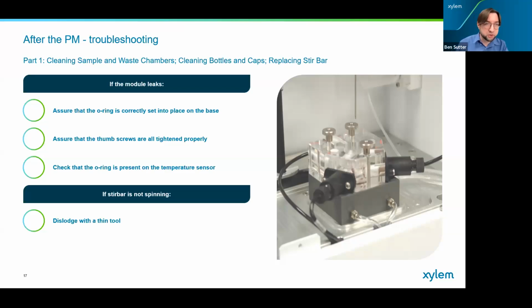We will watch Jason actually perform that action later. We want to assure that the thumb screws are all tightened properly. If those aren't all tightened properly, it won't make a seal with the O-ring and we'll have leaks. Make sure that the O-ring is present on the temperature sensor. I'm sure Jason will remind you of that one because that is probably the easiest O-ring to forget. And the second thing that could potentially happen is your stir bar is not spinning. This typically doesn't happen right after preventive maintenance, but it happens often enough that I wanted to mention it.